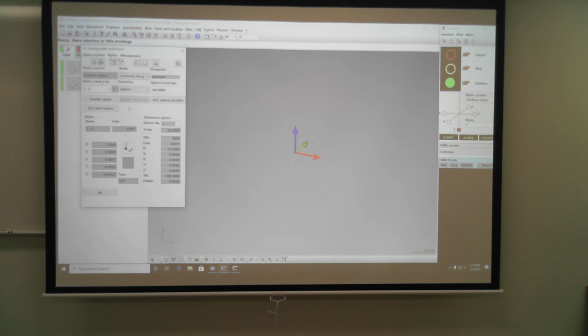And that's a really quick way of seeing if one of your probes got whacked. Is it going to be as accurate? No. But you're kind of not really checking for high accuracy or high precision when you do that. You're just trying to make sure one of your probes didn't get bent.